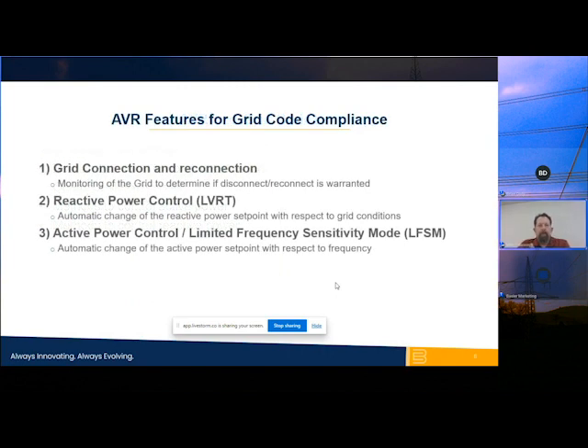Again, the three main components. First, grid connection and reconnection. We're going to monitor the grid to determine when a disconnect or reconnect is warranted. We are going to control the reactive power for grid stability, and we can automatically change the reactive set point with respect to those grid conditions. You'll also hear the term low voltage ride through. So we'll talk a little bit about low voltage ride through, as well as the overall reactive control component dependent on grid conditions. And also the active power control, or the real power control. We'll discuss a little bit the limited frequency sensitivity mode. This is an automatic change of the active power, or the real power, set point with respect to the frequency.